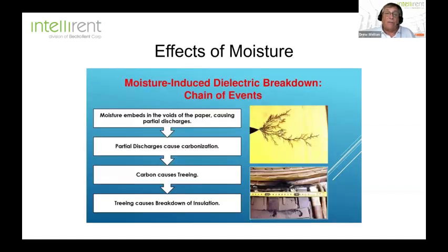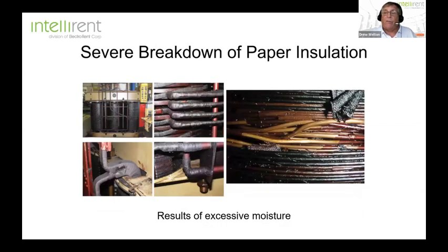Okay, so to summarize, the moisture embeds itself in the voids of the paper, creating partial discharge, and that will cause carbonization. You can see here that it creates this treeing effect and eventually leads to complete breakdown of the insulation, as you see in this particular picture. And here's just an example of certain failures that we had in the insulation because of excessive moisture.